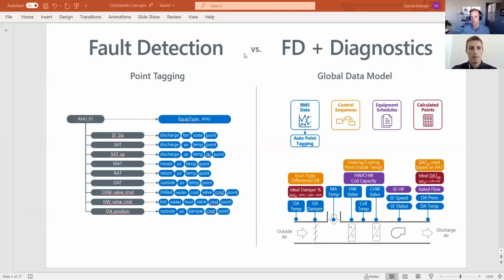Looking at this point list and trying to understand if your outside air damper is in an ideal state is really difficult. The BMS controller has a list of objects, and I tried to reverse engineer this. I see there's a return air temperature, maybe that's used in part of my economizer sequence. But to actually go through and apply that equipment type in your data model itself opens up more analytics capabilities. You can check for more things if you know the purpose behind this piece of equipment, and that higher level typing of the equipment and what it's supposed to be doing is critically important.